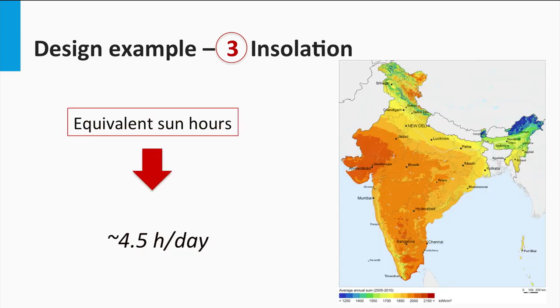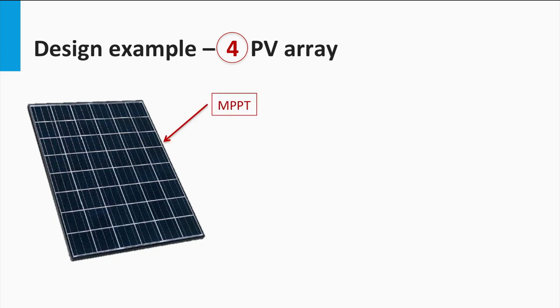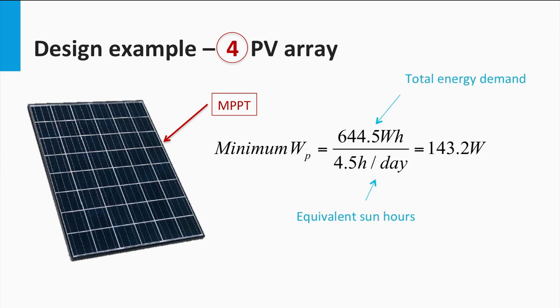Next, we consider the irradiance. Going by the same example as in the standalone system case, a location in India is considered with an average of 4.5 equivalent sun hours. Let's look at the electrical specification of an available PV module. It is a 100 Wp rated module with the given voltage and current parameters. Now, we need to find out how many of such modules are required to power the loads. Assuming that the panel would be operated at its maximum power point, we can find out the required number of panels as follows. We can first calculate the amount of minimum PV power required by dividing the total energy demand at the PV array output with the equivalent sun hours. Thus, the minimum PV power required is 143.2 Watts.